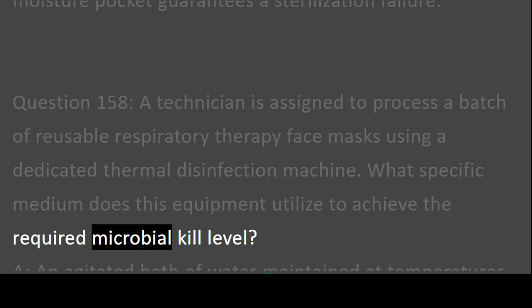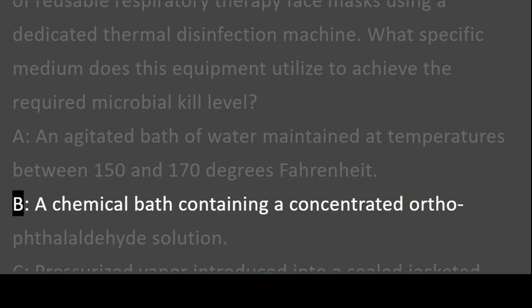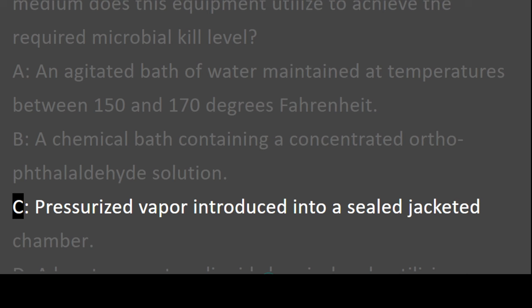What specific medium does this equipment utilize to achieve the required microbial kill level? A. An agitated bath of water maintained at temperatures between 150 and 170 degrees Fahrenheit. B. A chemical bath containing a concentrated orthophthalaldehyde solution. C. Pressurized vapor introduced into a sealed jacketed chamber. D. A low-temperature liquid chemical cycle utilizing stabilized peracetic acid.